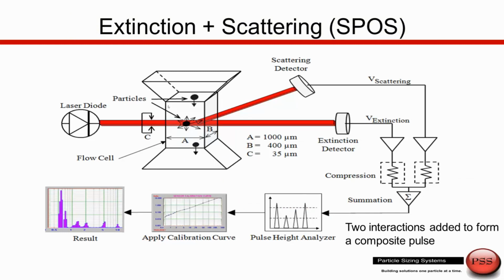But the sensor we put in our system is actually more sophisticated. Here is the extinction detector, or obscuration detector. In the AccuSizer LE400 sensor, we have also added a scattering detector. This allows us to measure down to smaller particle sizes. So we have these two detectors in our sensor. We take both of these pulses, sum them together, then go through the pulse height analyzer, which we also call the counter, and with use of a calibration curve, one at a time we count and size these particles. So this is a development beyond pure extinction, using extinction and scattering, and this is a technique of single particle optical sizing, and this is the sensor we would use for these measurements.